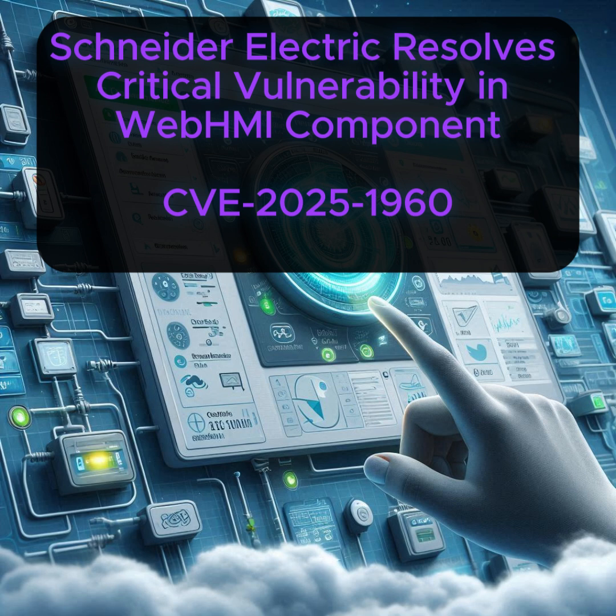So this vulnerability is classified as initialization of resource with an insecure default. Now, that might sound like a mouthful, but what it really means is that these affected systems, and we're talking about the EcoStruxure Power Automation System user interface and EcoStruxure Microgrid Operation Large, specifically those using WebHMI versions 4.1.0.0 and earlier, come shipped with insecure default settings, basically weak passwords, like really weak passwords. Yeah, like leaving the front door wide open with a big neon sign that says, "Come on in."